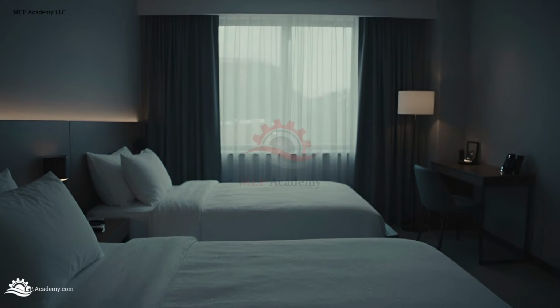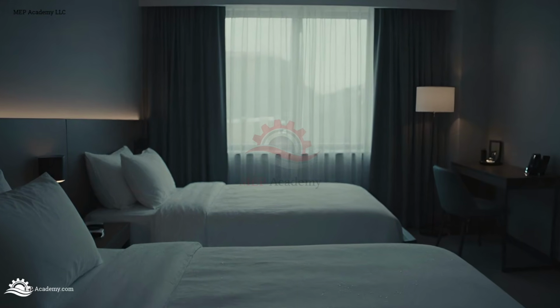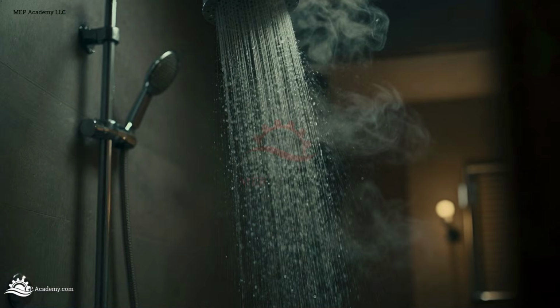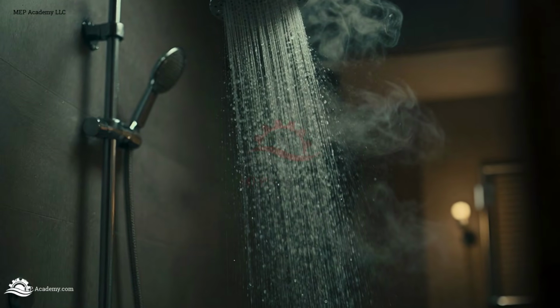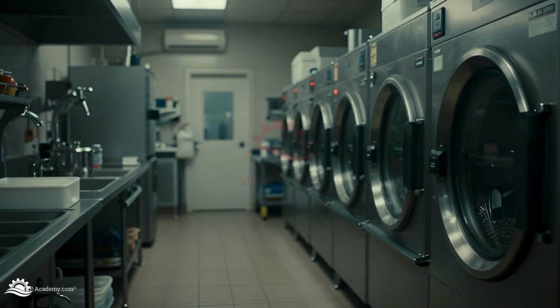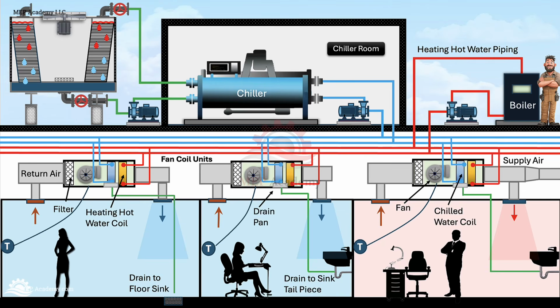A hotel may need chilled water for guest rooms, corridors, kitchens, and meeting spaces, while also needing domestic hot water for showers, laundry, kitchens, and cleaning. In a conventional system, the chiller removes heat from the building and rejects that heat through the condenser water system and cooling tower. At the same time, the boiler may be burning fuel to create heat somewhere else in the building. So, the building is paying to remove heat from one place, and then paying again to create heat in another place. A heat recovery chiller changes that story.